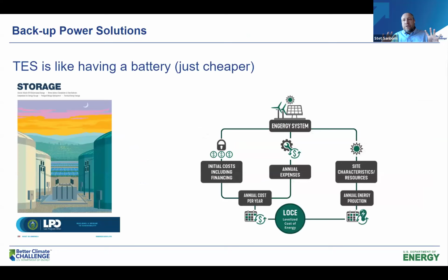The last thing that I want to share is that, and this might be beyond what our typical auditor is going to provide you, but we always like to look at solutions that are going to give us more resilience as well. So battery storage obviously helps with resilience during a power outage, but so does thermal storage. If you have enough on-site power backup to run pumps, thermal storage can give you several hours of additional conditioning without the heat pumps even running. And from an overall life cycle levelized cost of energy, which is a model that we run for all of these scenarios typically, thermal storage comes out ahead. It's a great solution to get you right-sized equipment on day one, reduce that electrical infrastructure upgrade, but still provide you all the benefits of a GHG reduction and resilience.